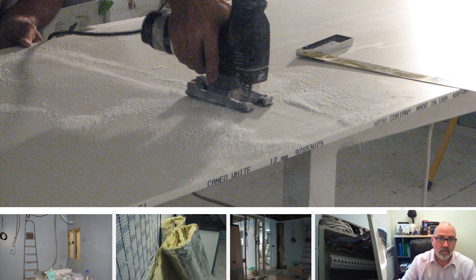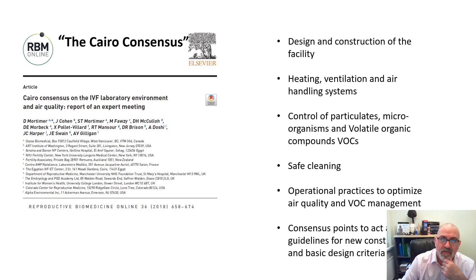With a growing body of evidence and the diverse nature of IVF labs, an expert meeting in Cairo convened to establish a consensus on recommended technical and operational requirements with aspirational benchmarks. They examined design, air handling, particle control, furniture, cleaning and VOC management, aiming to minimize exposure to harmful compounds. They listed measured VOCs in both old-style and modern IVF labs — the most common was ethanol, followed by isopropyl alcohol and acetone. Total VOCs in old-style labs were four times higher than in modern ones.